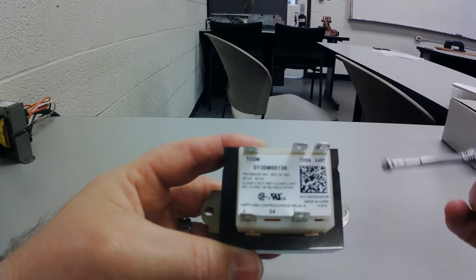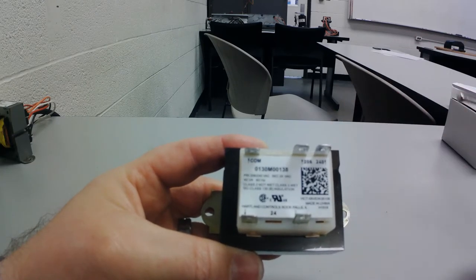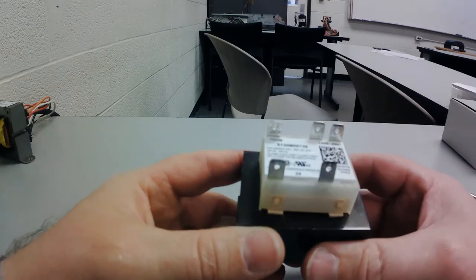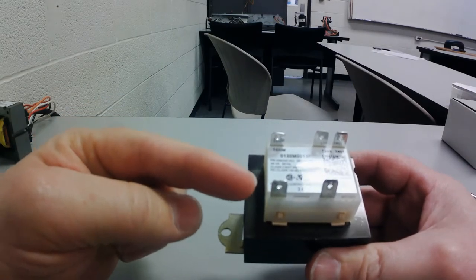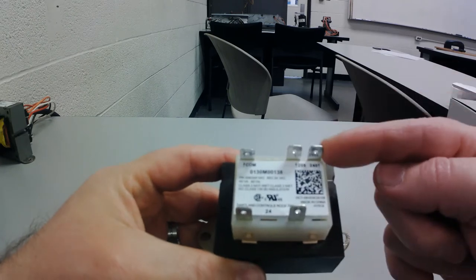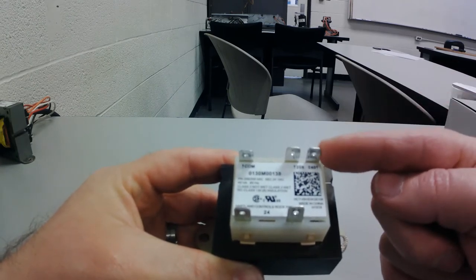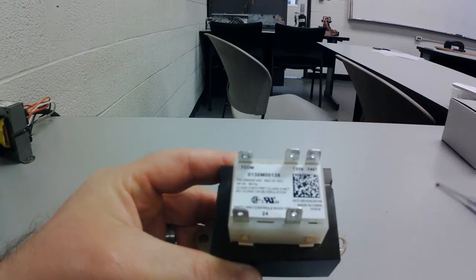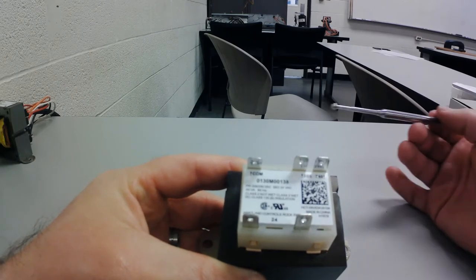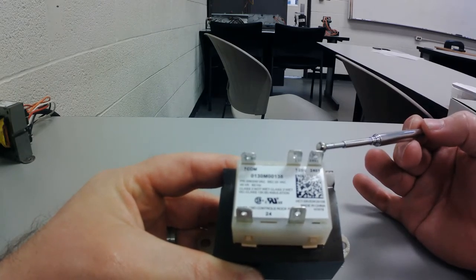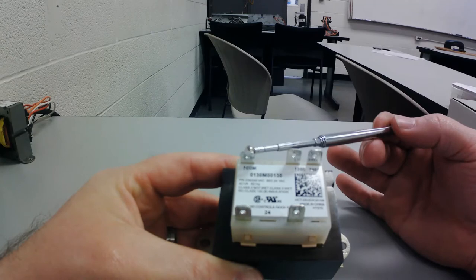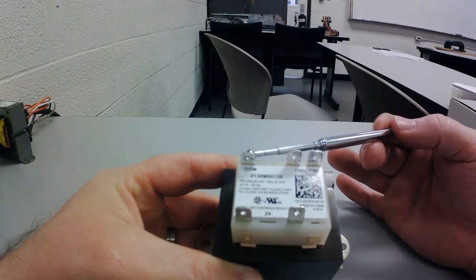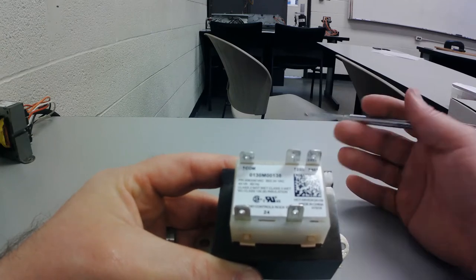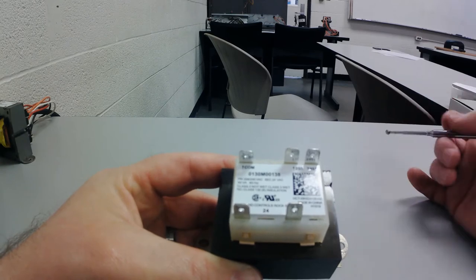No matter which power source you're using, you're always going to use this one as your return path back to power. And you can see down here at the bottom, we got our 24 volt terminals. So two terminals down here on the low voltage side, and I have three up top. I'm only going to use two of the three. So if I were using a 240 volt power source, I would use the outer terminal labeled 240, and my return back to power would be the common. The 208 would be left uncapped or unused.